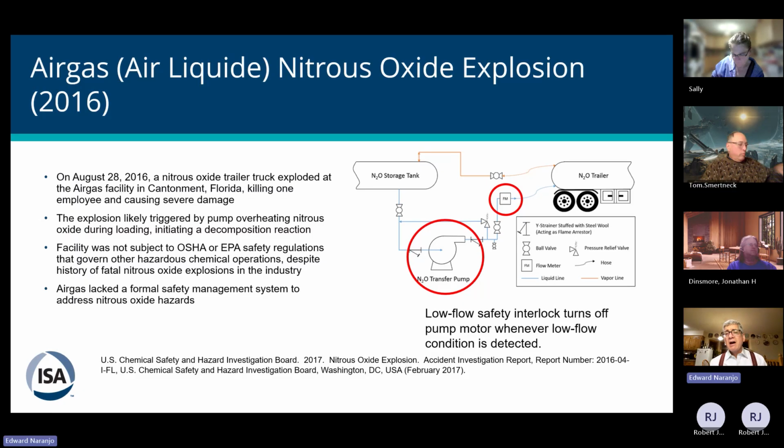Now, the U.S. Chemical Safety Board pointed out something that is very pertinent. PSM has a number of requirements for facilities. The very first one is, if you're subject to PSM, you must perform a process hazard analysis, or PHA. And you need to review that PHA at a minimum every 5 years. That's by law. If you're in the United States, that's the law of the land.